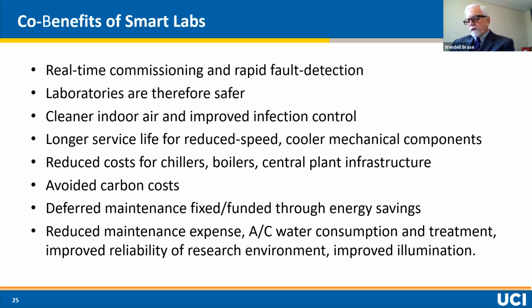Real-time commissioning and fault detection and making laboratories safer are two sides of the same coin. Laboratories are safer because we discover faults within minutes or hours at the most. Some of those faults probably could have gone on for decades in a university in the old paradigm, where we didn't have this kind of informatics. We consider a laboratory a safety machine. A good machine operates with precision, and it has precision fault detection. That's why our laboratories are safer, and we have the data to prove it.